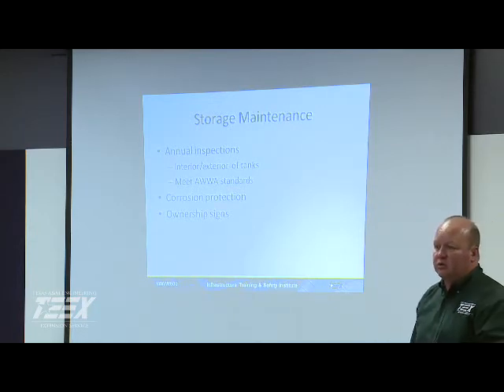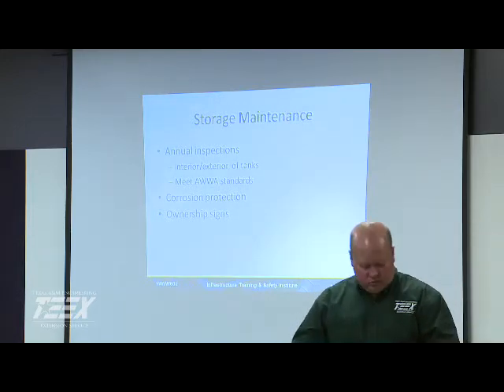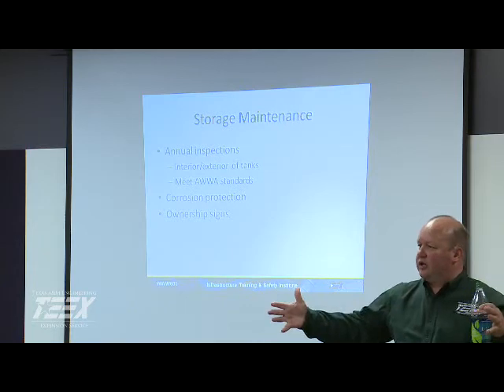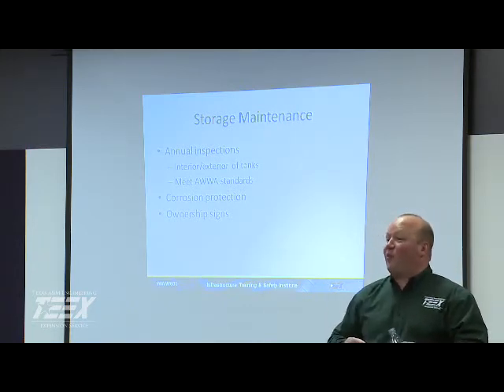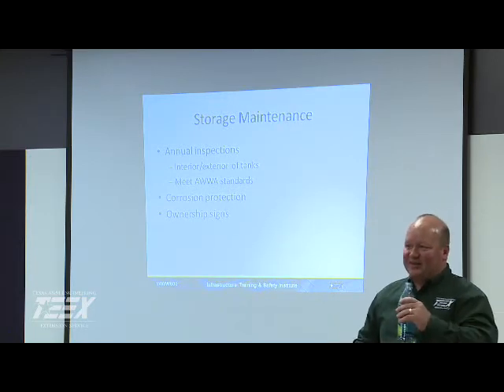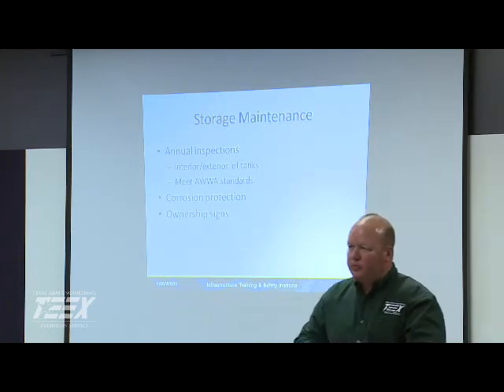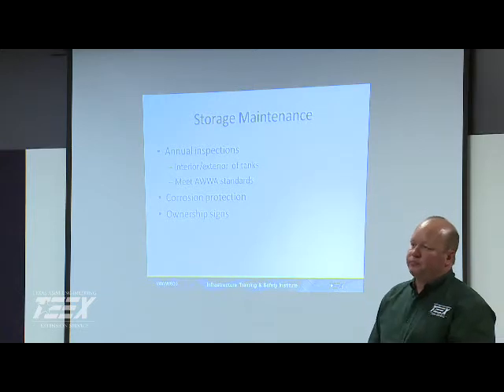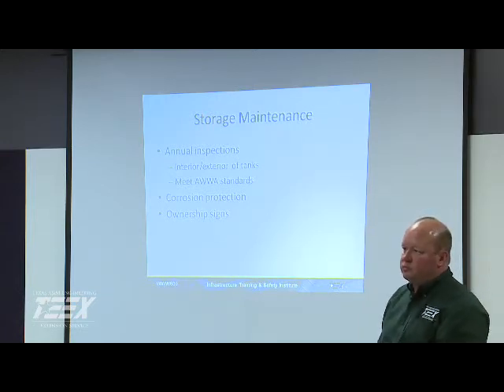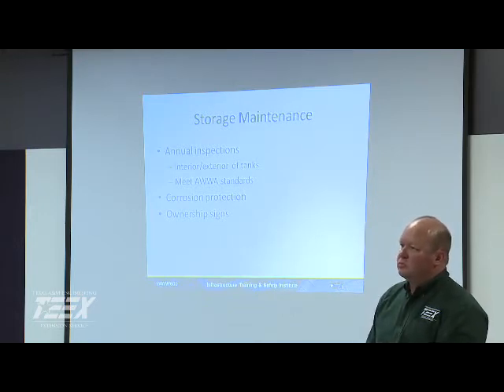We had two of them painted 4 years ago. How long are you looking at? Are you looking at a 10-year cycle? That's the first time I've painted it since I've been here. Ever? Oh, wow. Well, usually we go on the 5 year tank inspections. That's all we usually do, like a paint analysis. And if they recommend that it be painted, then whenever we do our inspection, we'll say we recommend that you follow through with the tank inspection recommendations.